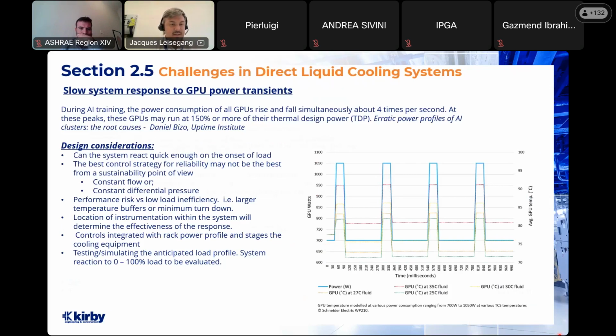And then from a testing and simulating point of view, simulating the anticipated load, having those load banks in the system which can give you that instantaneous reaction, that 0 to 100% load. How does the system then react to that onset of load? And are we confident that that system reacts quick enough?